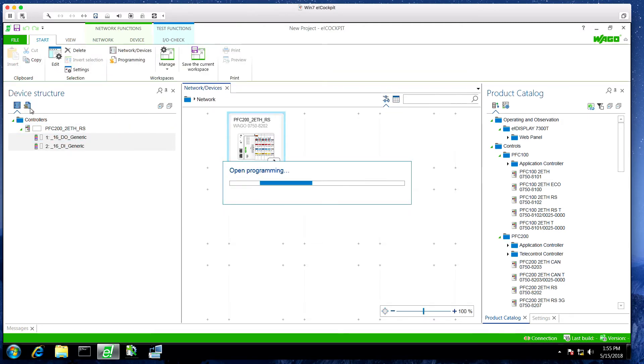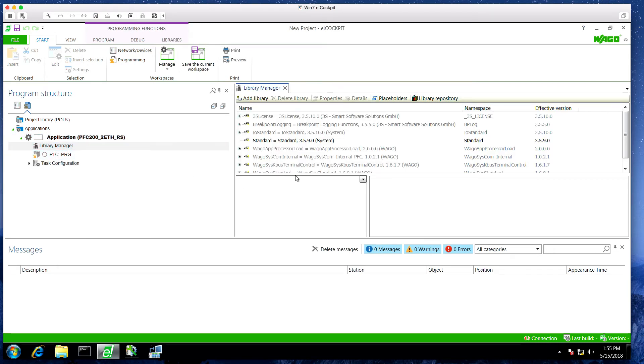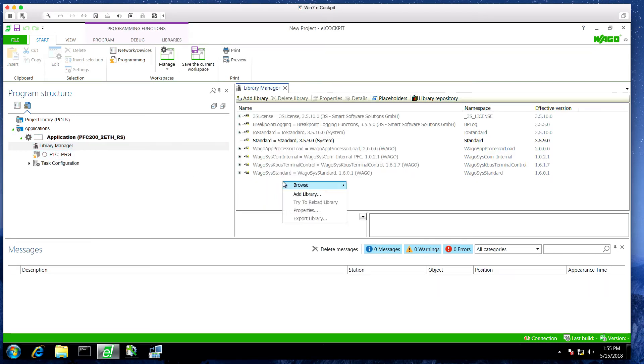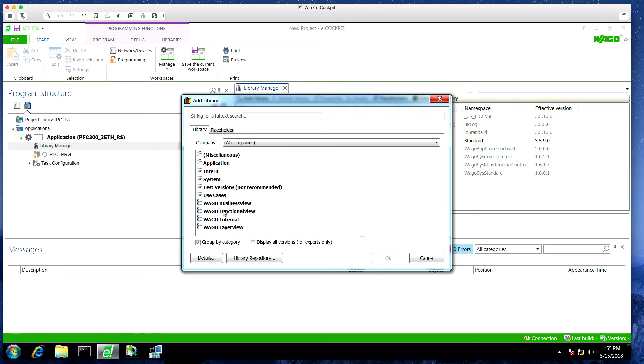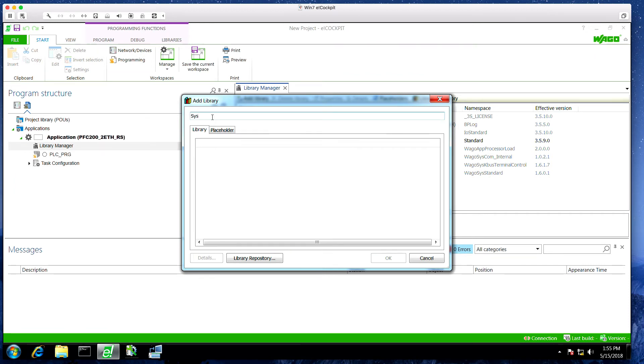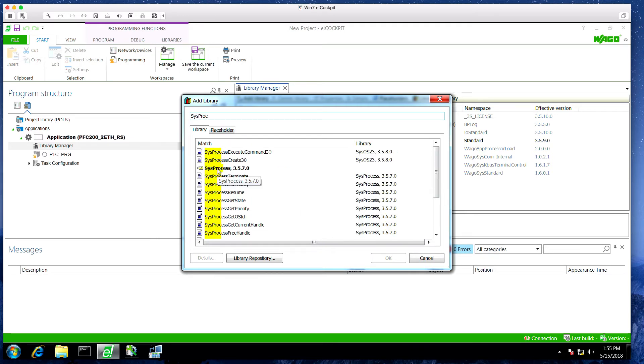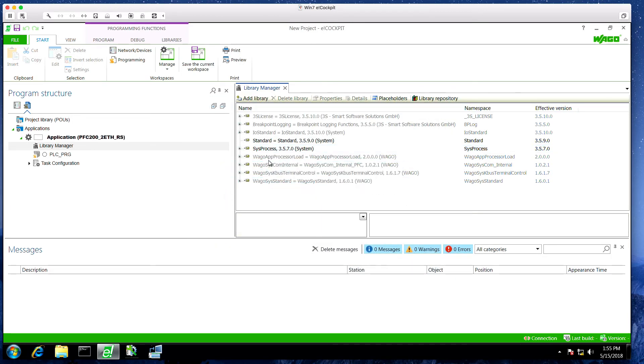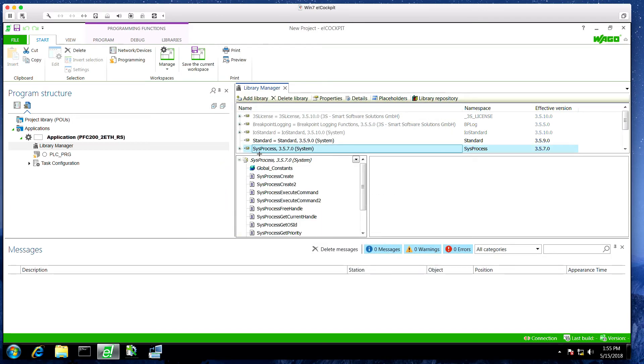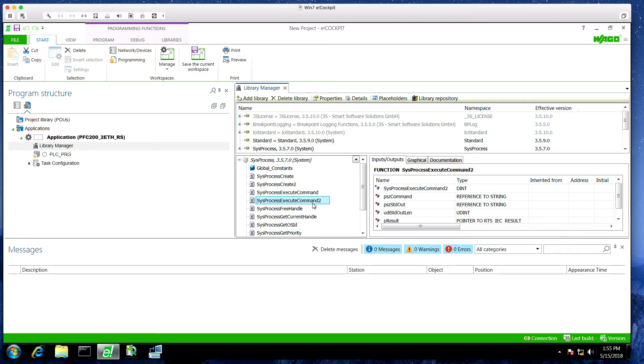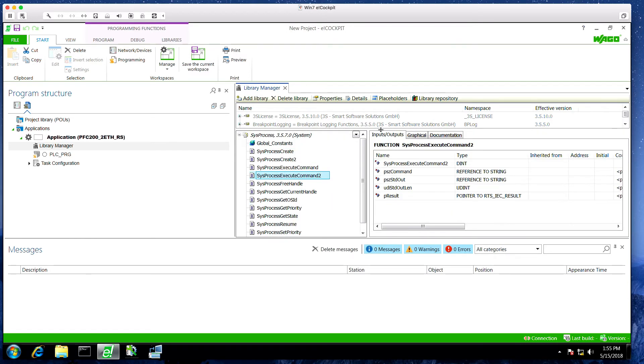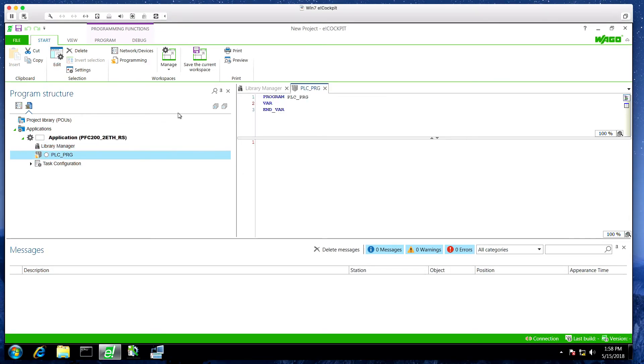I can go to the programming window. I need to go to the library manager and add a library to this that will allow me to invoke shell scripts. I'll go to the library manager advanced, add a library advanced. The library I'm looking for is the sysprocess library. This has a lot of different things in it to interact with the Linux environment. The one POU that I'm going to use is sysprocess execute command 2, and this will allow me to invoke my shell scripts. This is a function, so we don't need to even create an instance of it. Once we've added this library, now we can go to our PLC PRG.